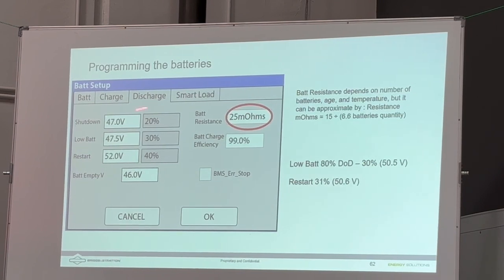Okay, the last step on the programming of the batteries, so the shutdown voltage is the voltage at which, this will probably be a percentage for most installs, especially the communicating batteries, but it's the percentage or voltage at which you want the loads to be turned off. So for instance, let's suppose that you don't want to drain your batteries below 10% state of charge. Then you would put 10% here, and whenever you get down to 10%, and the grid is not there to supply the power, a grid down situation, it will shut loads off when you hit 10%. You can set it to 0% if you want.